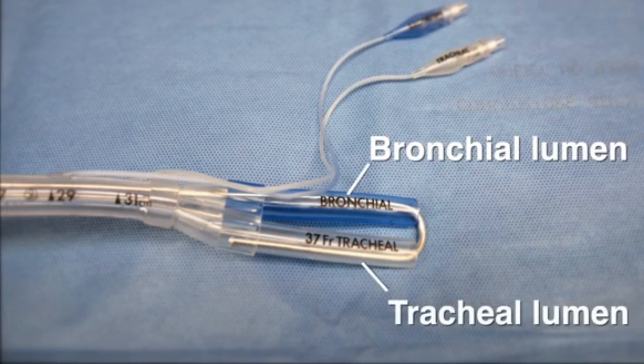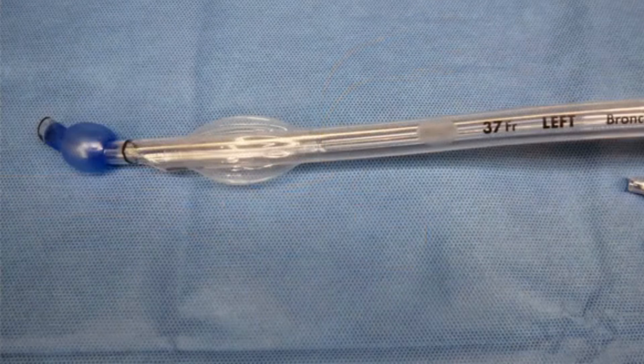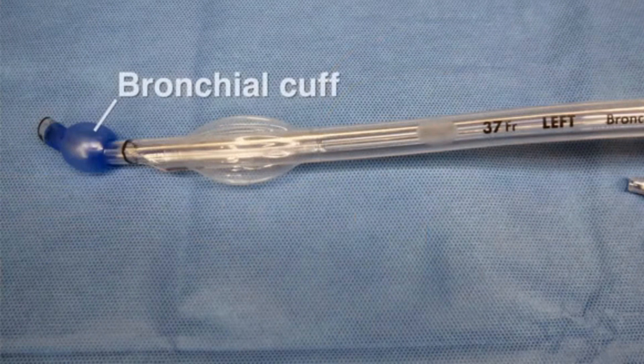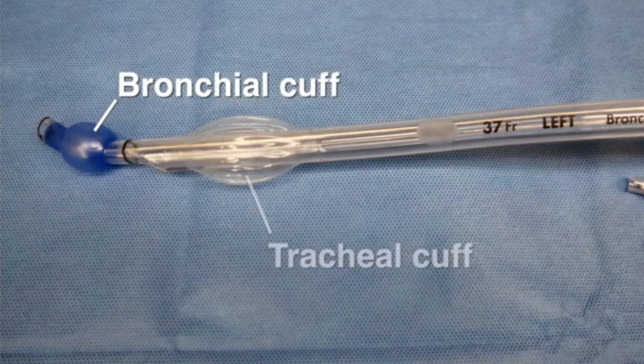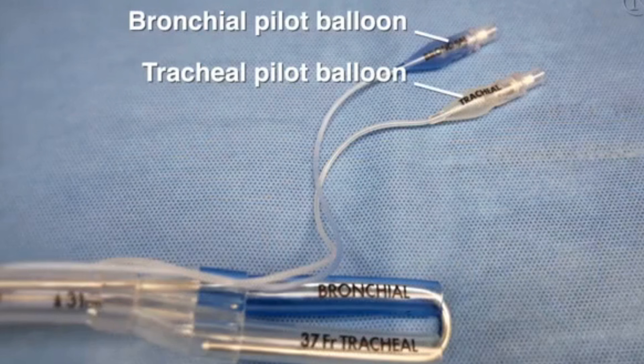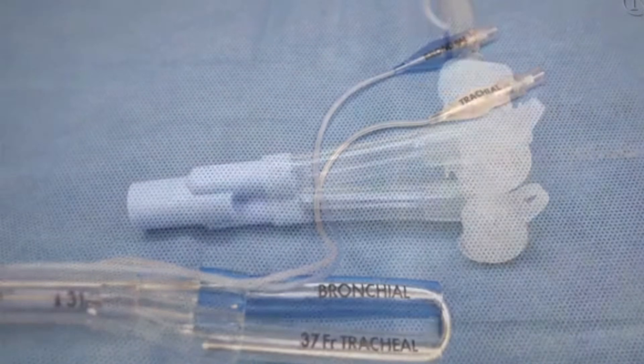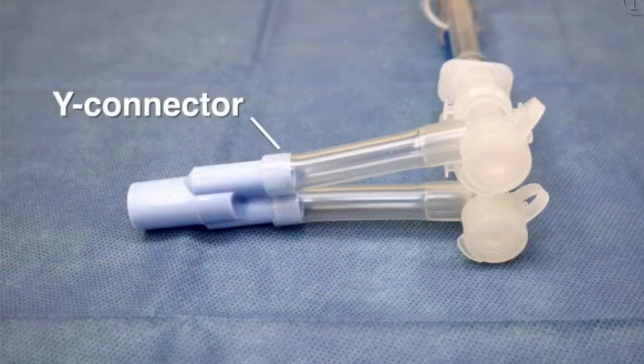The tracheal lumen is designed to be placed above the carina. Each lumen has a color-coded cuff, which is often blue on the bronchial lumen and clear on the tracheal lumen. Each lumen also has a color-coded pilot balloon. A Y connector connects both lumens to the breathing circuit.